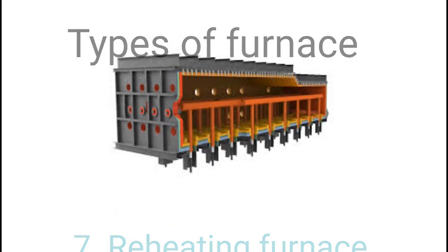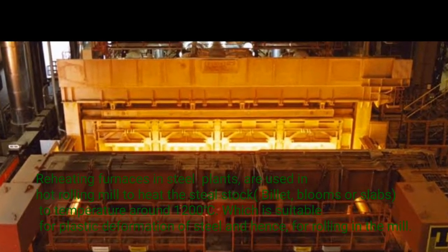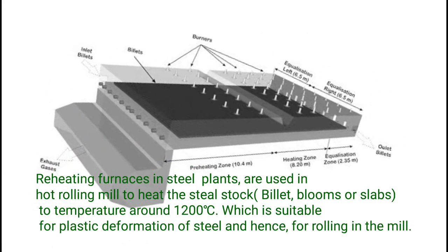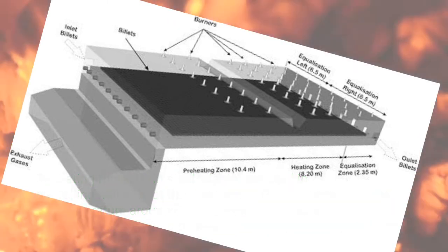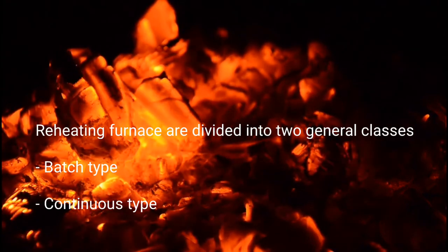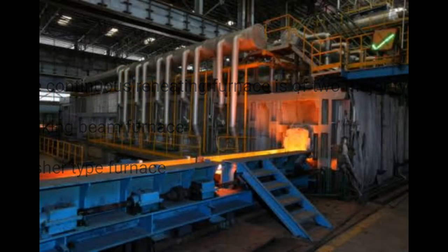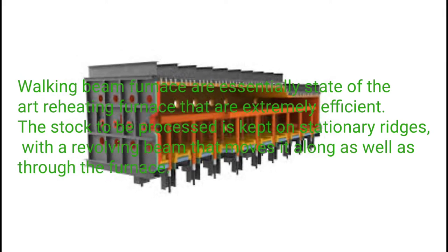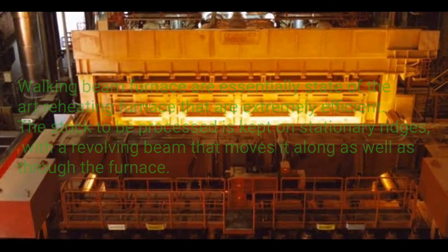Type 7: Reheating Furnace. Reheating furnaces in steel plants are used in hot rolling mills to heat steel stock — billets, blooms, or slabs — to temperatures around 1200°C, which is suitable for plastic deformation of steel and hence for rolling in the mill. Reheating furnaces are divided into two general classes: batch type and continuous type. The continuous reheating furnace has two major types: walking beam furnace and pusher furnace. Walking beam furnaces are essentially state-of-the-art reheating furnaces that are extremely efficient.